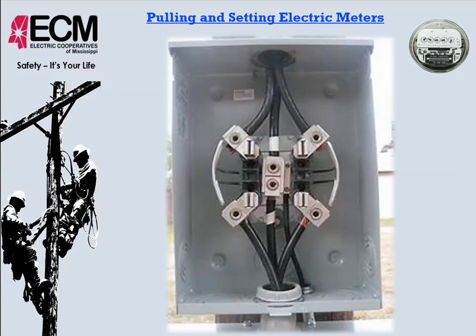This was a fairly decent job here. This is an overhead meter base. You see that the line side comes in, has a little bit of a curve here. Don't need to make this too abruptly, but it definitely curves in. Make sure that it lines up in here. If you come in more at this angle right here, you have to crook the wire right at the end. That's not good for the wire. It's going to make it more likely to break and cause problems down the road.